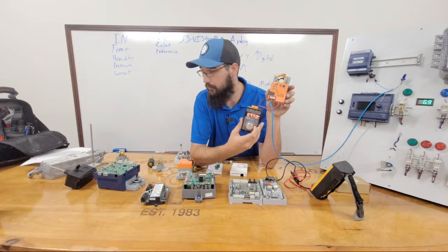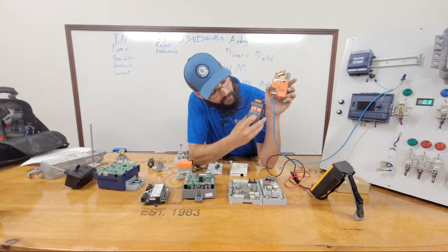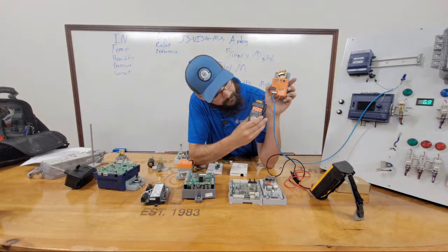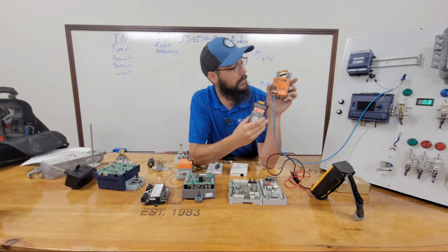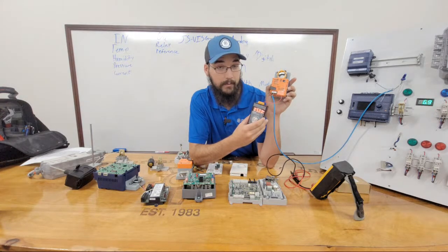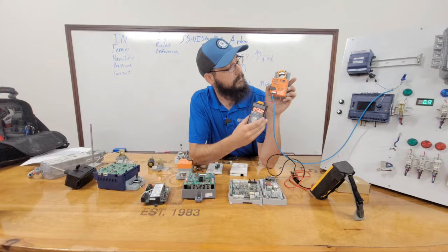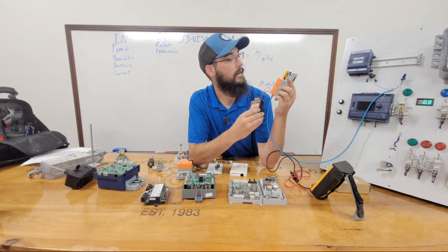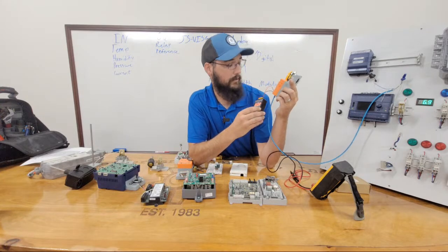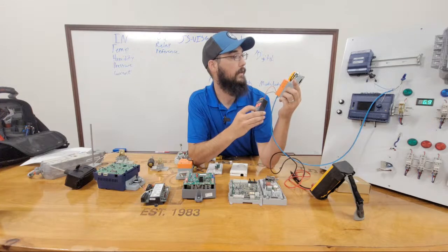Now I can vary this down, and I'm going to go to just say 5 volts VDC. All right, right there. So I'm going to expect that once that gets up to the 5 volt position, it should stop. And there we are. It says that's 5 volts, or that's 50%. It's not quite 50%.